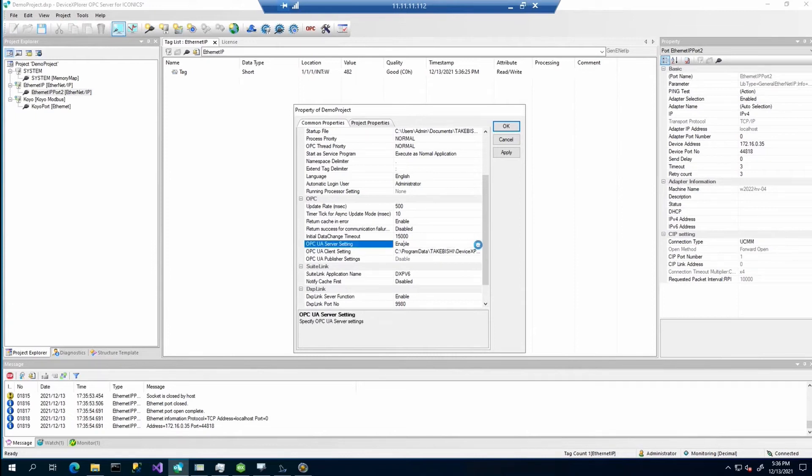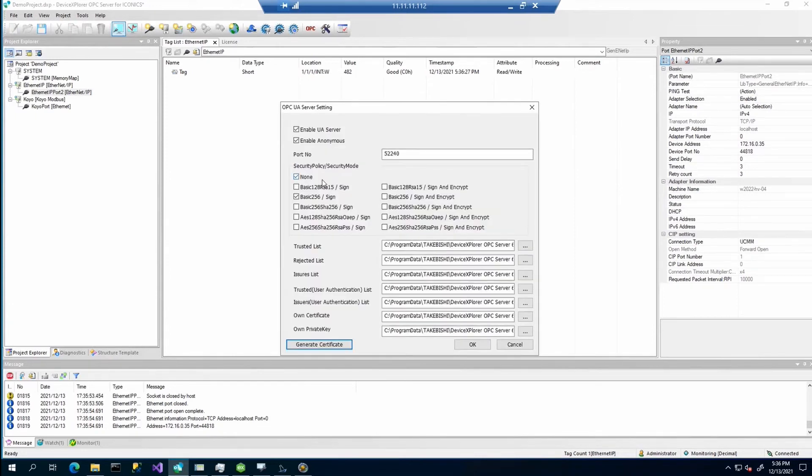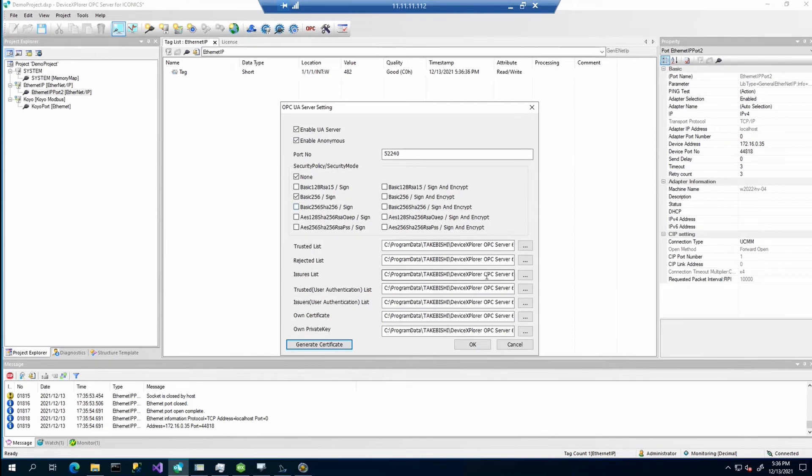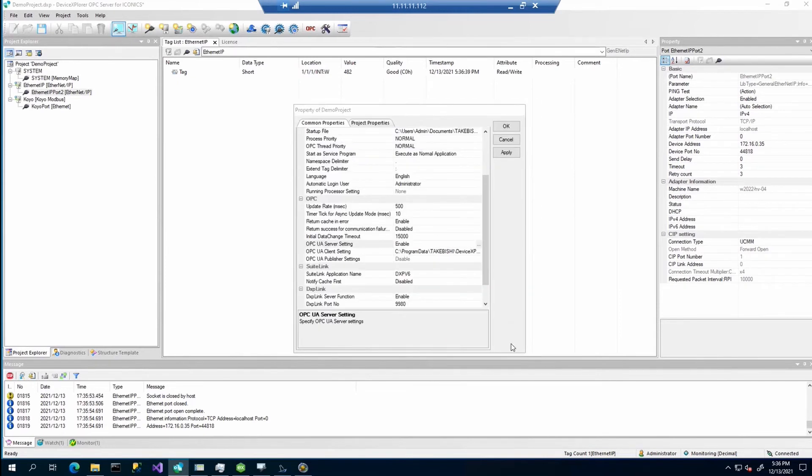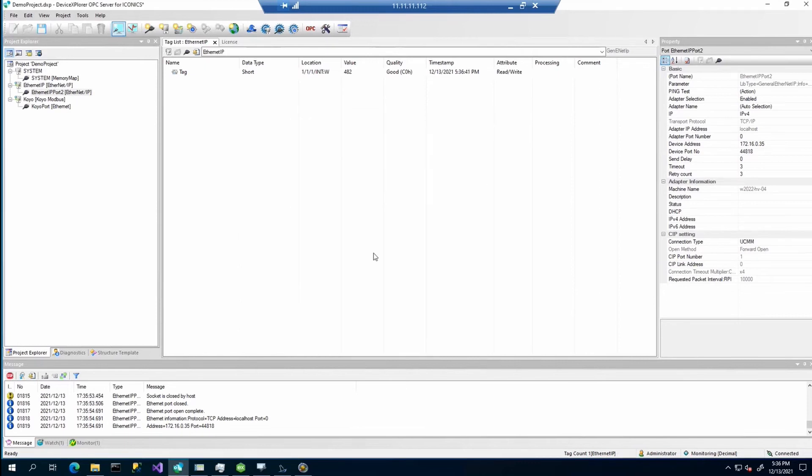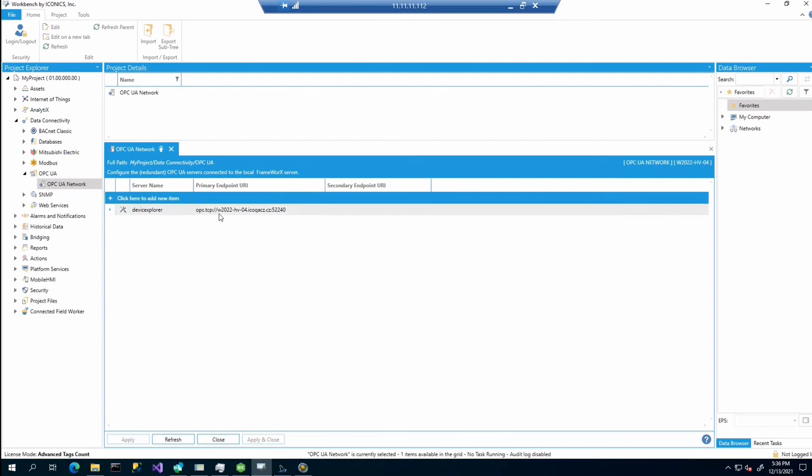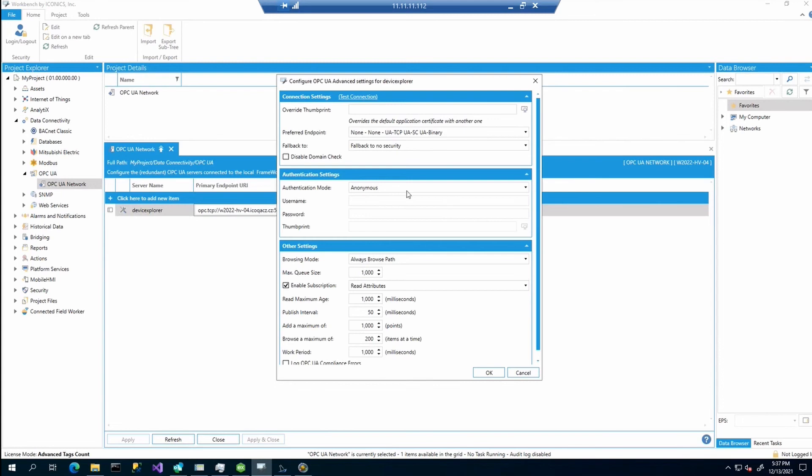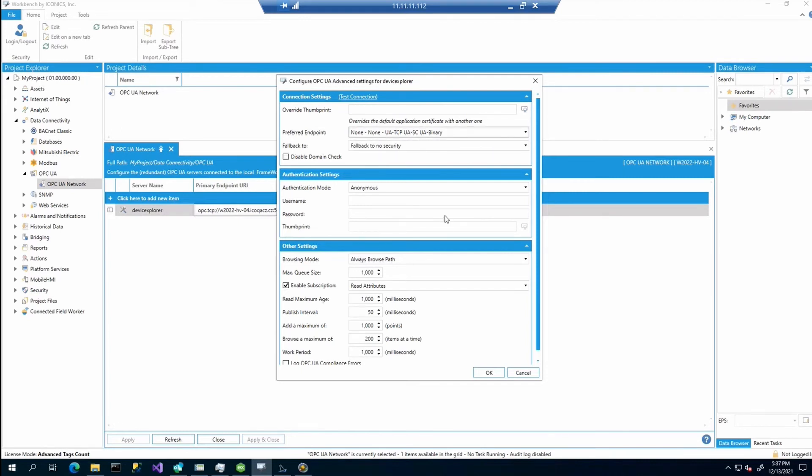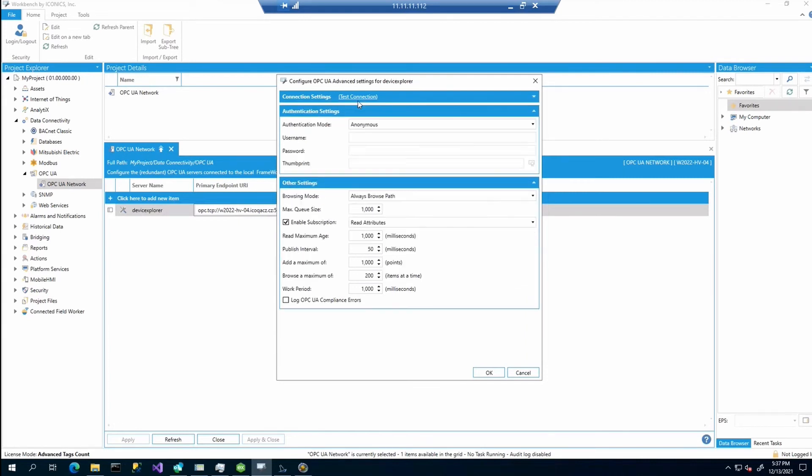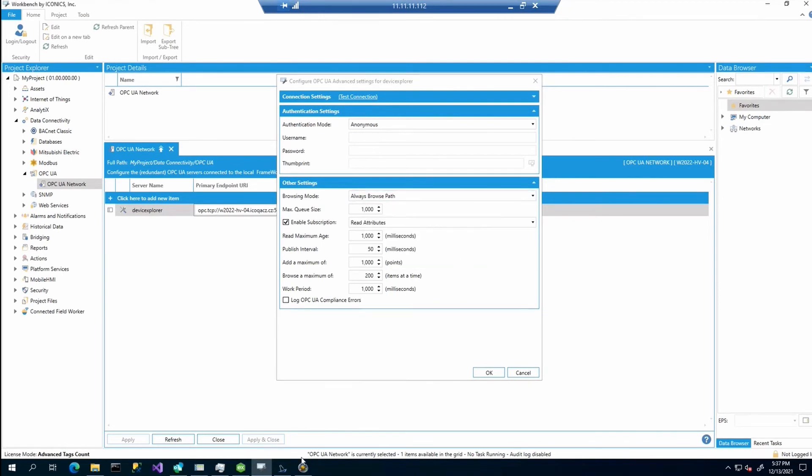So we can configure here whatever you need. I have enabled the UA server completely. And it will be anonymous. You can see the port and some other settings. So this was already predefined. After that, you need to configure also the connection from Genesis. So you will need to configure it in workbench. There is the OPC UA network configuration. You can enter the server name and the primary endpoint. If you click and everything is properly set, you can also select or pick the preferred endpoint. Once you are done, just click the connection and you can see that we are properly connected.